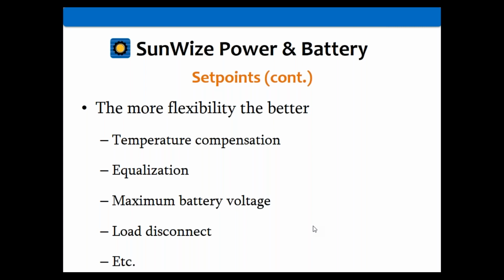We've got a whole tech note and webinar covering that before, but different batteries want different temperature comps. Some might want -5 millivolts per degree per cell, some might want -3 or -4. So it's nice to have a charge controller that allows you to adjust that, so you can dial that into your battery a little better and give it a bit more life. Equalization - most manufacturers don't recommend it, but some might want it once a year or so. So it's nice to have that either manual or automatic, especially if you can adjust it to say you only want it to equalize once a month or something. Having that capability might be useful.